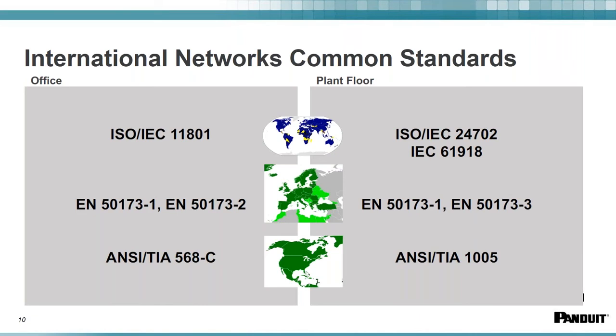Similarly, when you go to the Americas, you will find that on the office side, all communication networks are governed by the TIA 568 spec. And similarly, on the factory side, the TIA 1005 uses a lot of the elements that exist in the TIA 568, but also includes additional requirements for factory type operations, because the factory is a different environment.